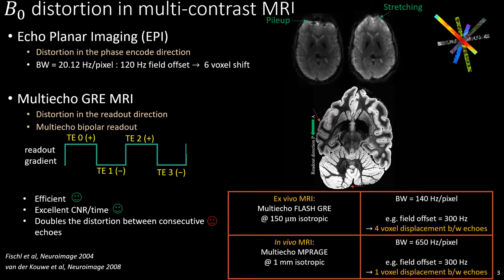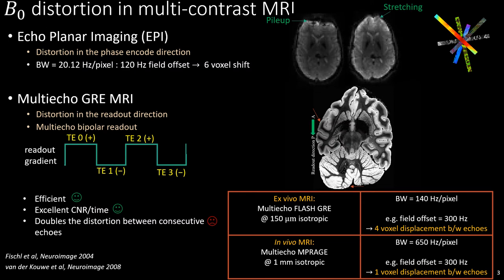For the ultra-high resolution multi-echo FLASH ex vivo MRI application, we use low bandwidth to maximize the SNR, but this induces large distortions, especially near small air bubbles, which are common in these preparations. While in vivo multi-echo MPRAGE distortions are much less, it is still common to observe at least a one voxel displacement in the temporal lobe and the sinuses.